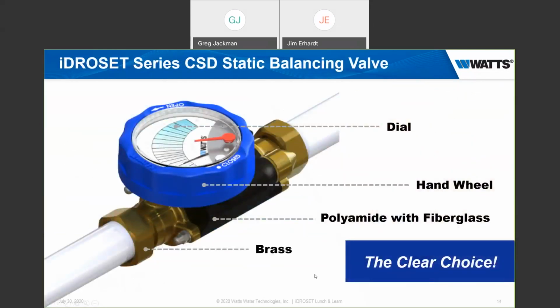So the iDROSET, we can look at it, and basically there are three functions in the basic construction of the valve. Number one, you'll notice there's a large dial on the top. That dial reads out the flow directly. In other words, you do not need an instrument to be able to tell what the flow is. It will indicate immediately as soon as the pump turns on. That needle will move, the black needle will move to indicate what the actual flow through that valve is.